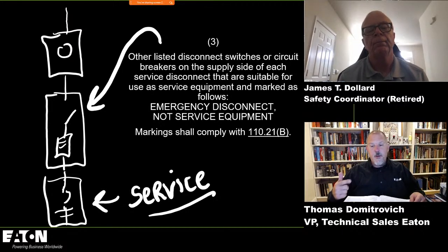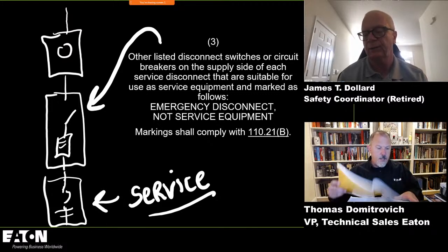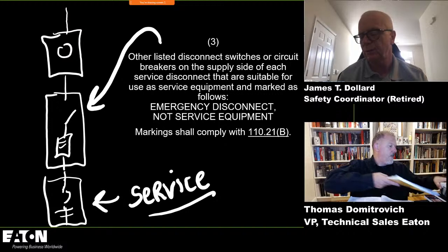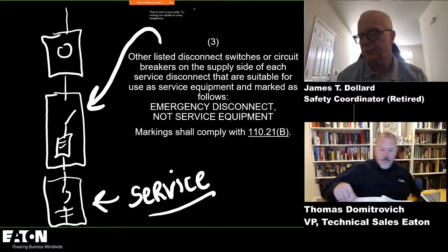Does 70E require a disconnect in front of a 480 volt meter? Do you know? No. NFPA 70E is a work practices standard. That's right. It can't get into installation criteria. That's right. It's outside of its purview.